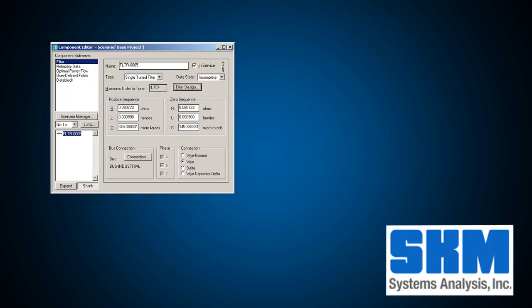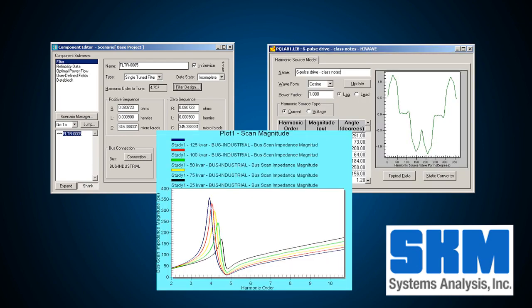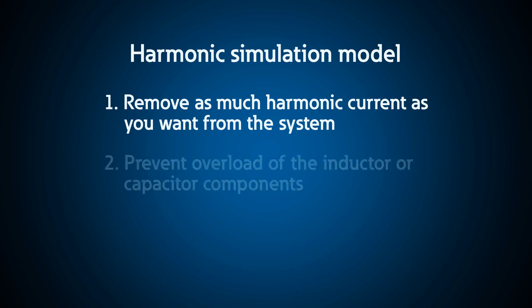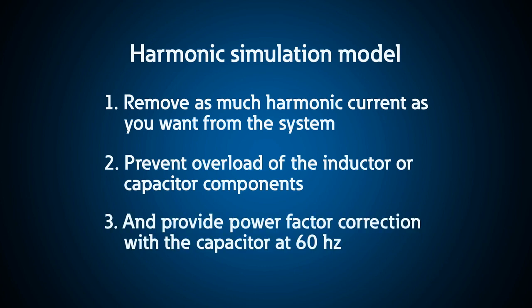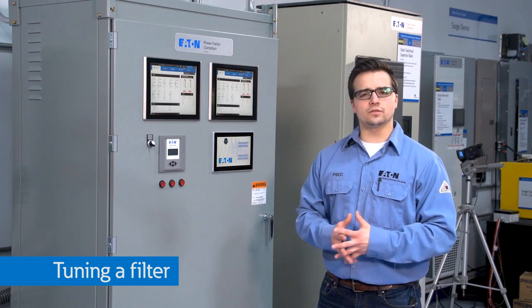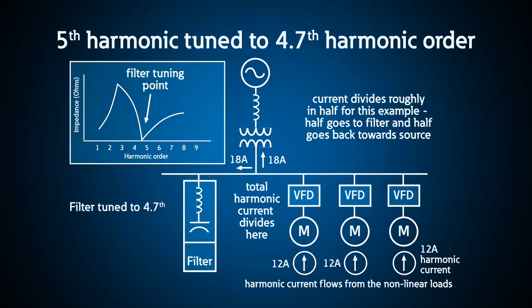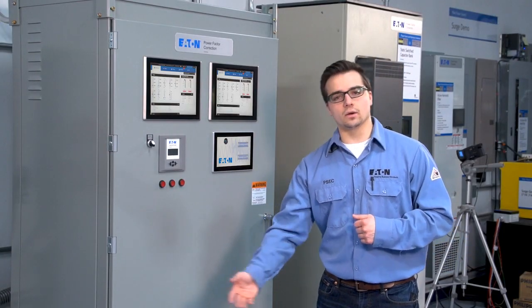Using software like SKM, you can model the filter components and determine the ratings so that you can: first, remove as much harmonic current as you want from the system; second, prevent overload of the inductor or capacitor components; and third, provide power factor correction with the capacitor at 60 Hz. When you tune a filter, you typically tune it below the frequency of interest. For example, for the 5th harmonic, we often tune a 5th harmonic filter to the 4.7th to capture maybe half of the 5th harmonic, or even the 4.2nd if we are less interested in filtering harmonics but more interested in providing reactive power or power factor compensation. When we purposely place these components in a circuit, we call this a harmonic filter.